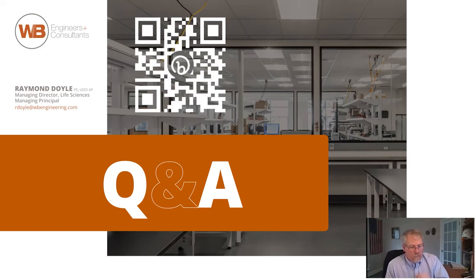That's in vacuum jacketed piping, which is about $1,000 a lineal foot. So there's a decision that needs to be made in your master plan when you start talking about cryogenic liquids, as to whether you want to have dewars delivered, which are basically tanks with liquid nitrogen in them, delivered to the points of use or lab spaces that need them, versus having a distribution system to each of those labs or floors from a bulk tank outside.